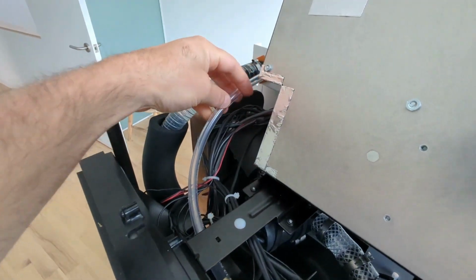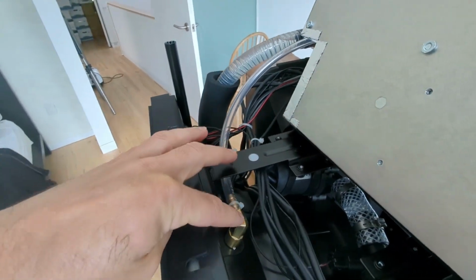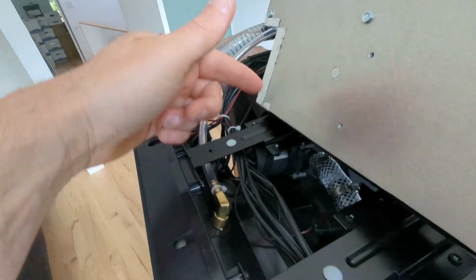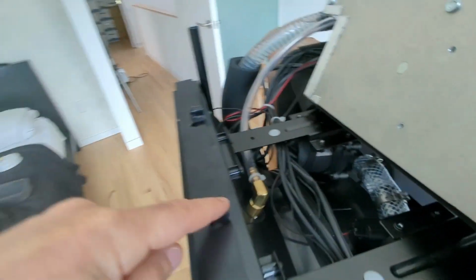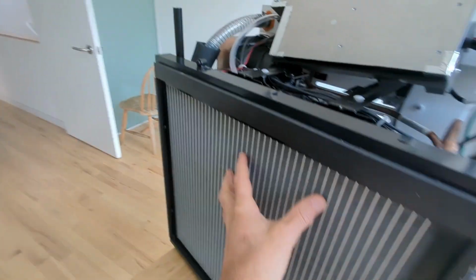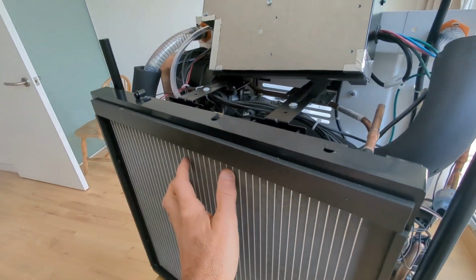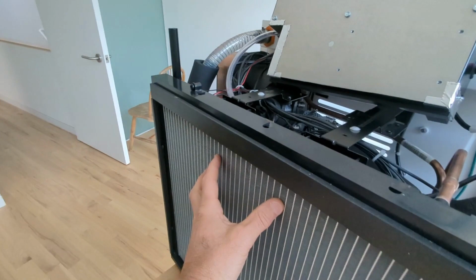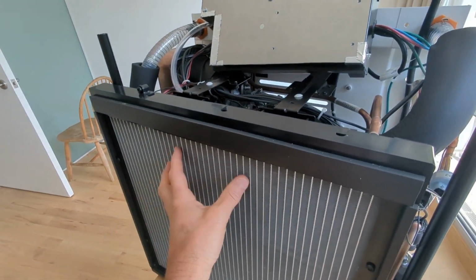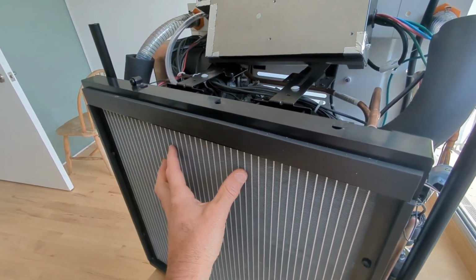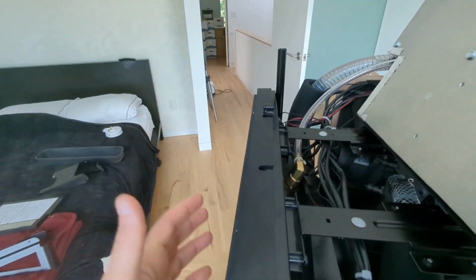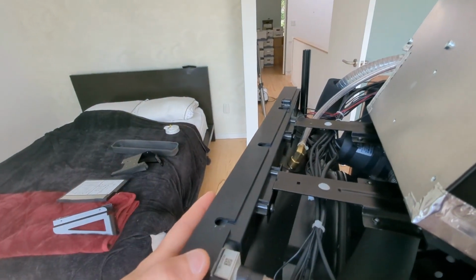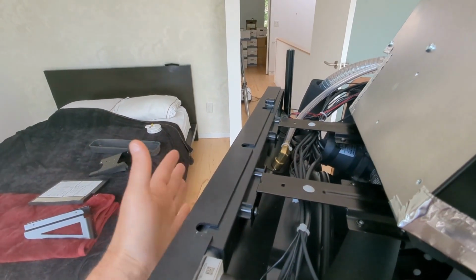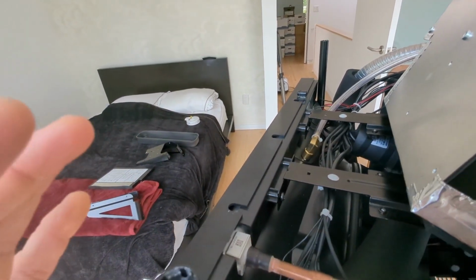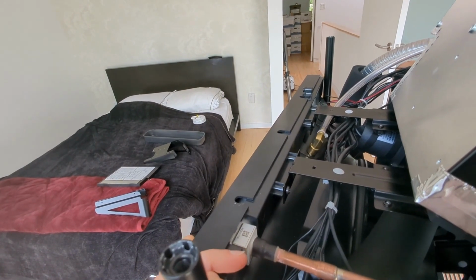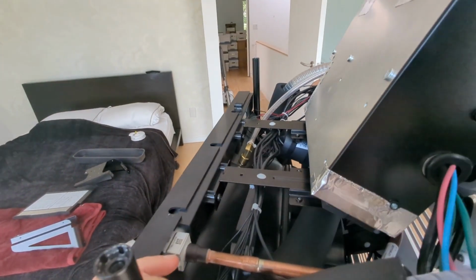All right, up here is a very interesting thing that I like. This is the condensate line that comes from the indoor unit, and in air conditioning mode, you're gonna have a pump in the indoor unit that's pumping that condensate water up into this hose, and then this drips it down onto the condensing coil. This is great because it means this condensing coil in AC mode is gonna be hot, because you're gonna have the hot gas flowing through here. So that condensate is gonna drip on this hot coil, and it's gonna evaporate because you have all this air blowing through and it's hot. It's just gonna evaporate and be gone. So you don't have any dripping condensate under any conditions, which is great.